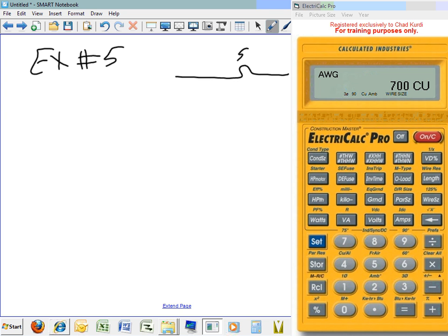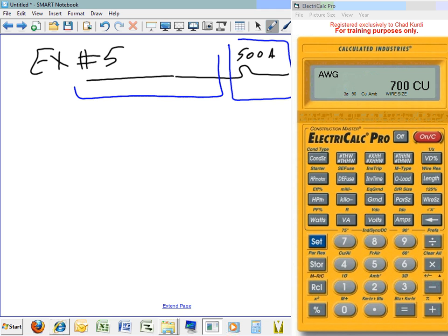Suppose I have a 500 amp feeder, and suppose my feeder goes to this disconnect switch. This is my gutter. Gutter, not your rain gutter. This is a gutter where they have conductors and you tap into them. Similar to these surface mounted gutters, you have conductors with a cover, you cover them, you extend the equipment. And this is a disconnect switch, 500 amp. And right in here, bud, I tapped, look at that, just tapped. And I went and I fed some equipment.